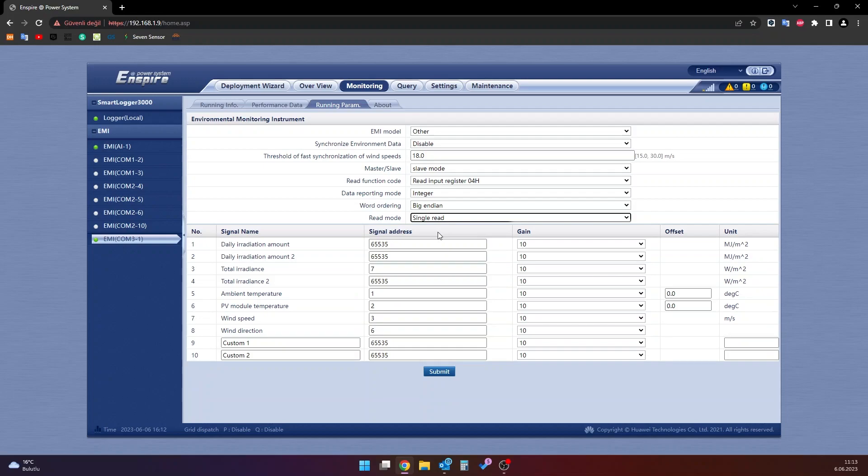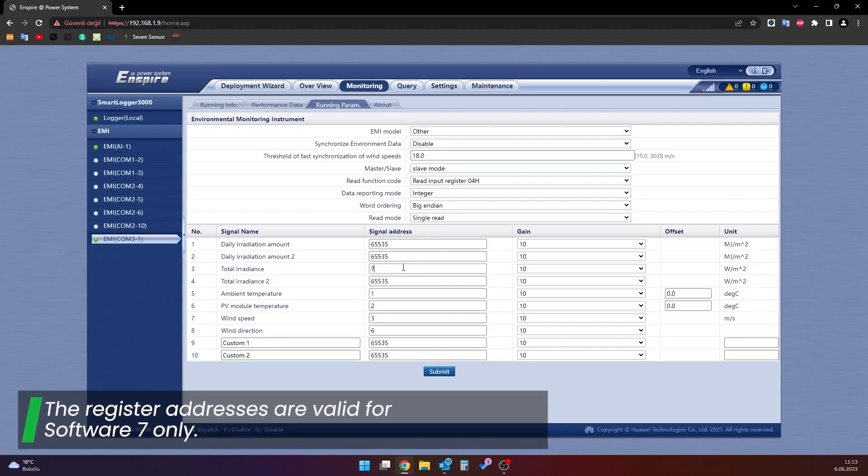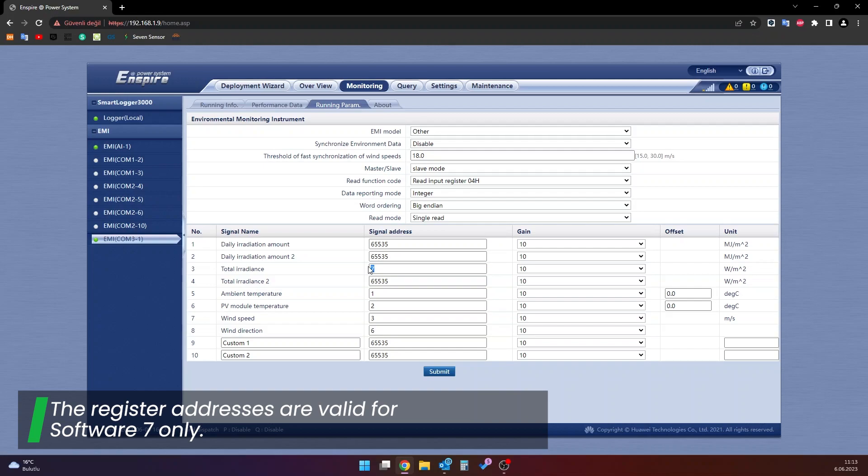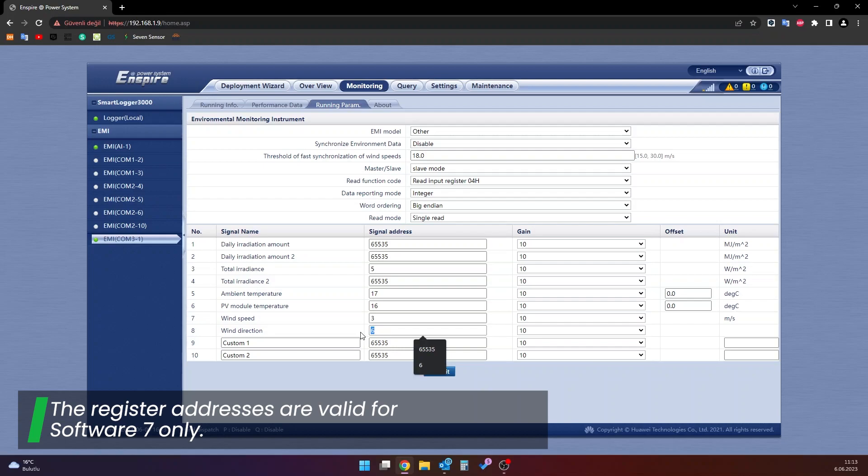To the total irradiance section, the register is 5. To ambient temperature section, the register is 17. To PV module temperature section, the register is 16. To the wind speed section, the register is 3. To the wind direction section, the register is 19.